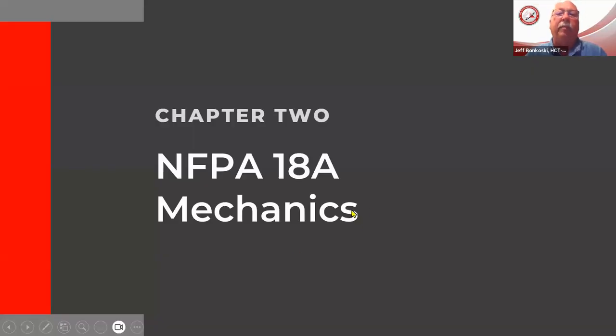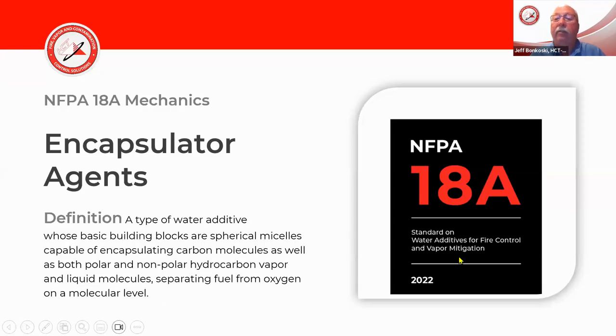We get into the NFPA 18A. This is the NFPA standard on water additives for fire control and vapor mitigation. What other standard are you aware of that NFPA has that will work on flammable or combustible vapors to control a fire? I don't know of one, even with 27 plus years in the fire service.